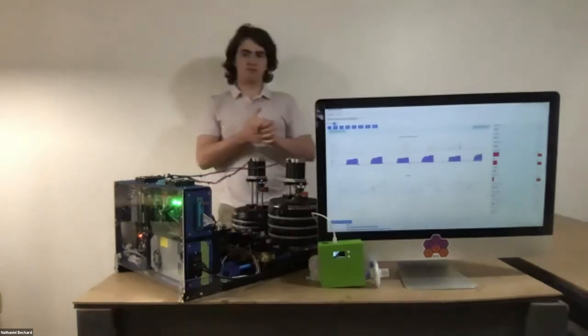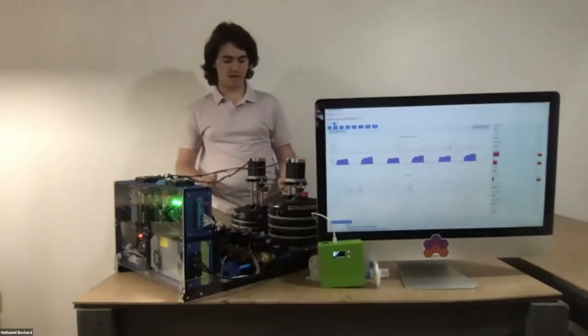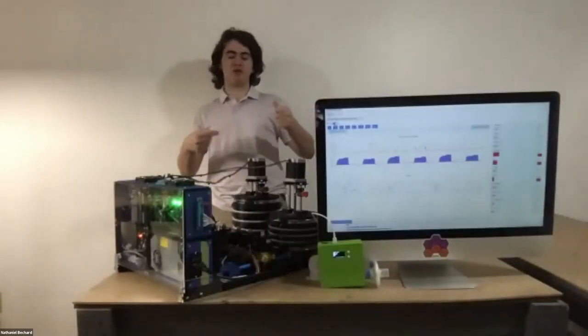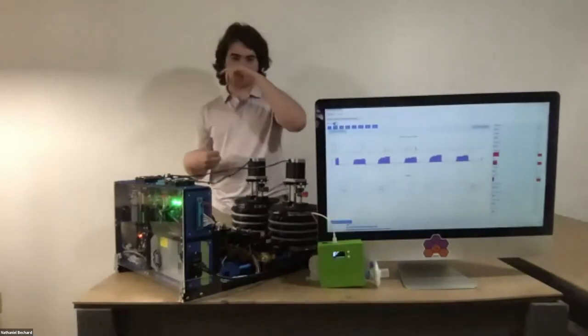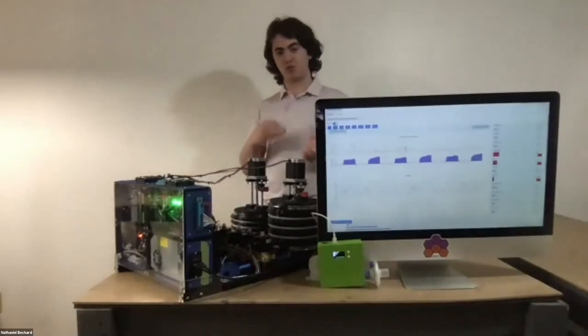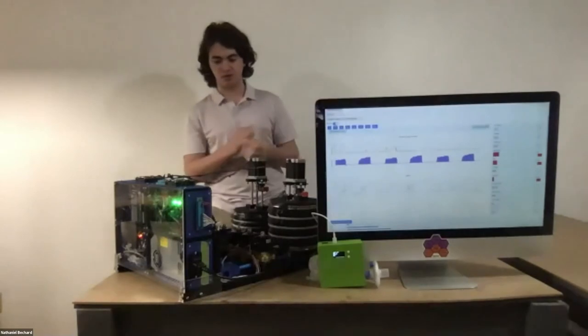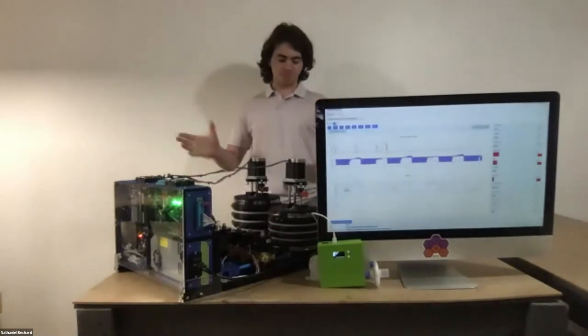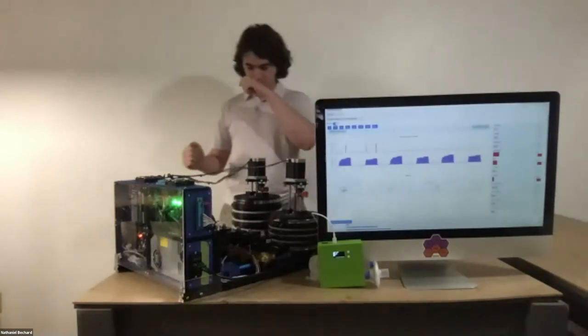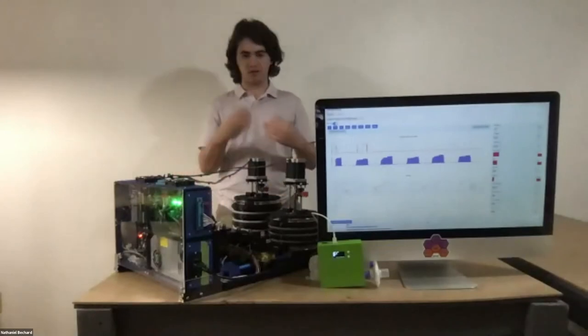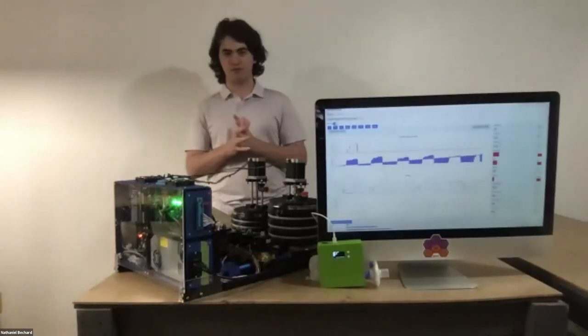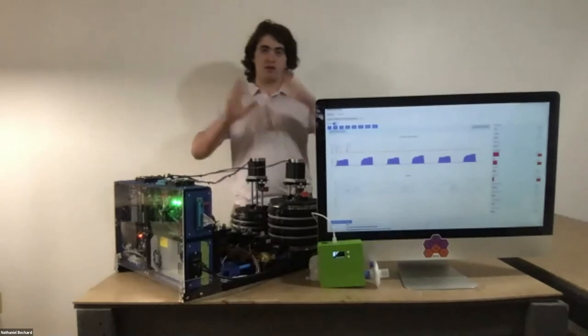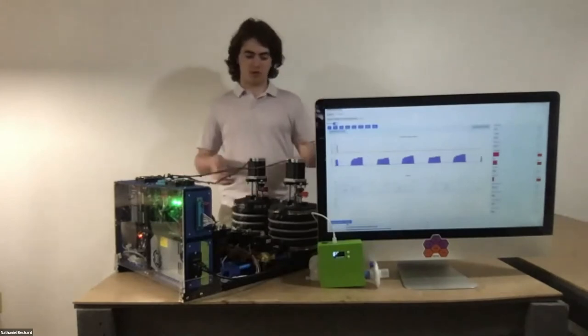Great. So yeah, that's really only on the upstroke here. You're sucking in oxygen for a portion of the time and you're sucking in air for another portion. That's how we control our FIO2, right? And I think that's really most of what there is to talk about within these 10 minutes for the technical part of the talk.